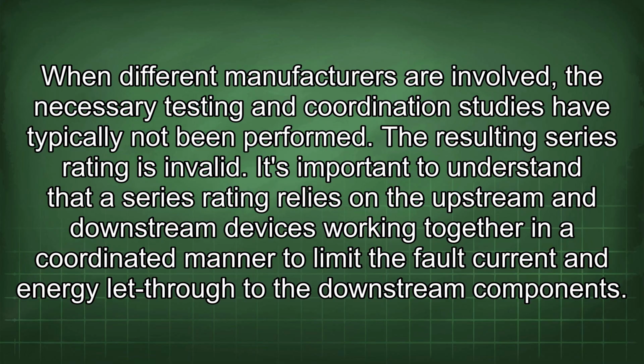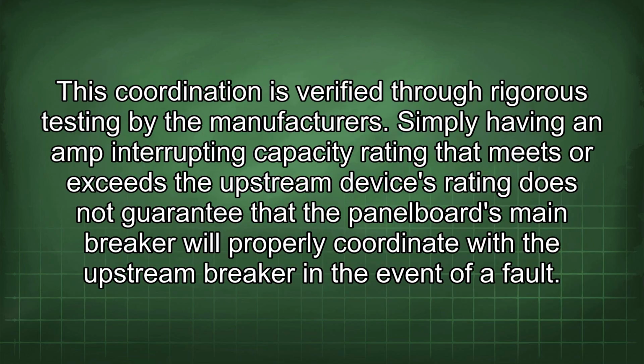It's important to understand that a series rating relies on the upstream and downstream devices working together in a coordinated manner to limit the fault current and energy let through to the downstream components. This coordination is verified through rigorous testing by the manufacturers. Simply having an amp interrupting capacity rating that meets or exceeds the upstream device's rating does not guarantee that the panel board's main breaker will properly coordinate with the upstream breaker in the event of a fault.